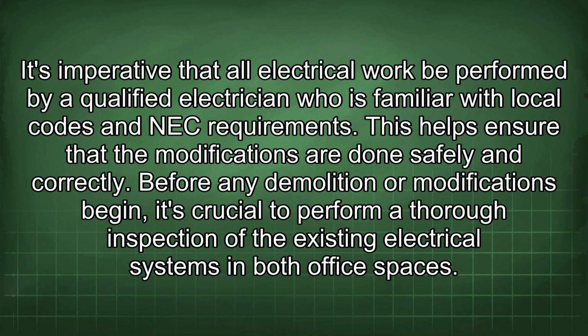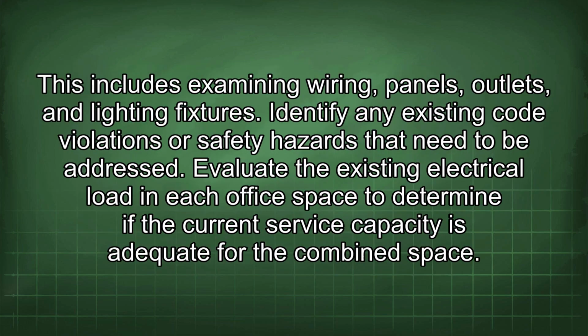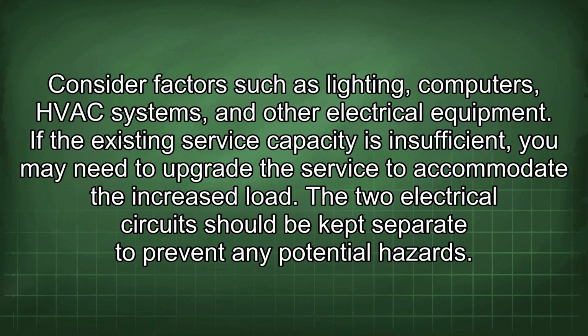Before any demolition or modifications begin, it's crucial to perform a thorough inspection of the existing electrical systems in both office spaces. This includes examining wiring, panels, outlets, and lighting fixtures. Identify any existing code violations or safety hazards that need to be addressed. Evaluate the existing electrical load in each office space to determine if the current service capacity is adequate for the combined space. Consider factors such as lighting, computers, HVAC systems, and other electrical equipment. If the existing service capacity is insufficient, you may need to upgrade the service to accommodate the increased load.